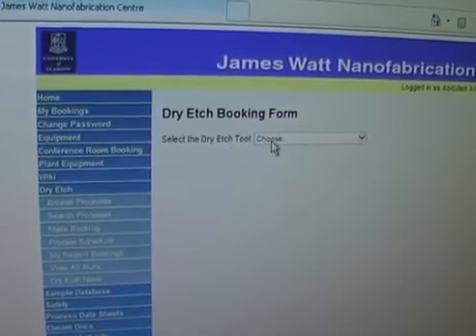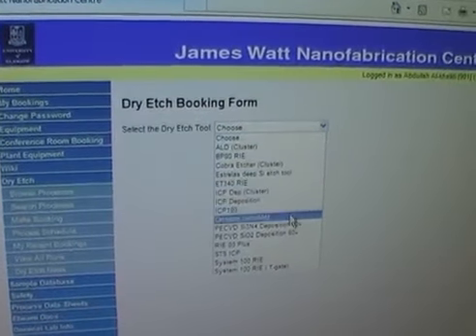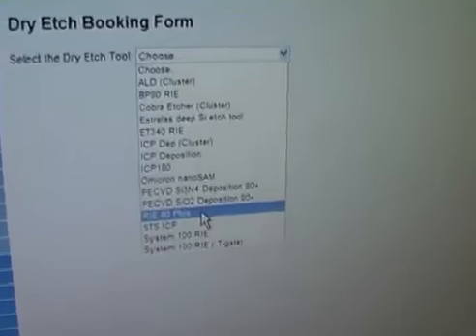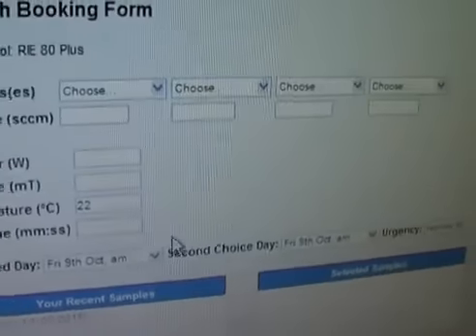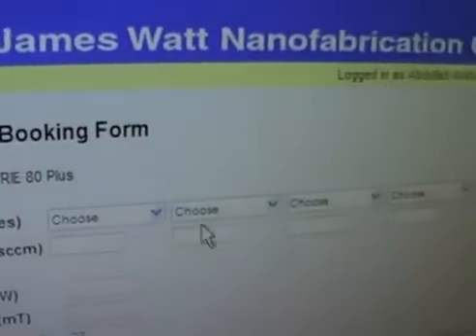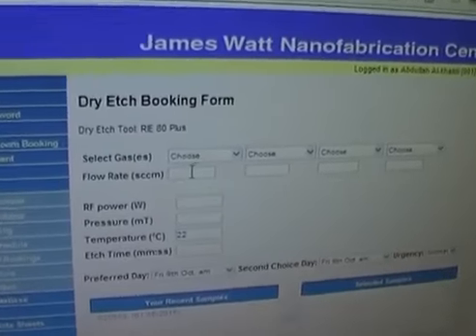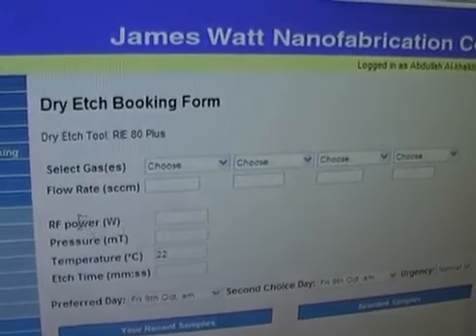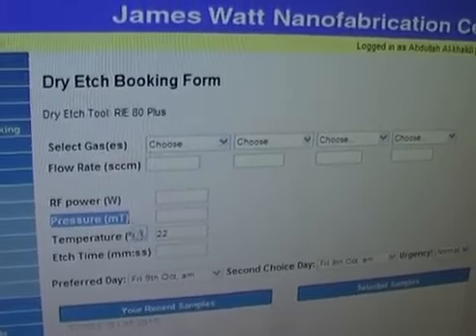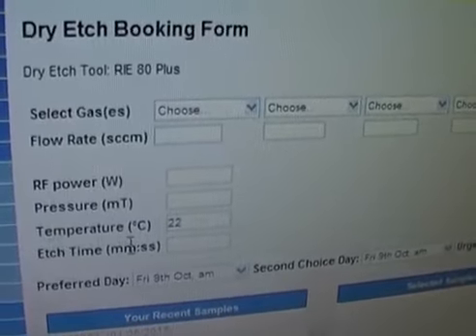Here we have the dry-etch tools, so we select the tool we would like to use. In our case, we will use the RIE 80 Plus. Here we have the selection of gases and flow rates — for every gas we choose, we set a flow rate. Then we have the RF power, the pressure in millitorr, the temperature of the chamber, and the etch time.